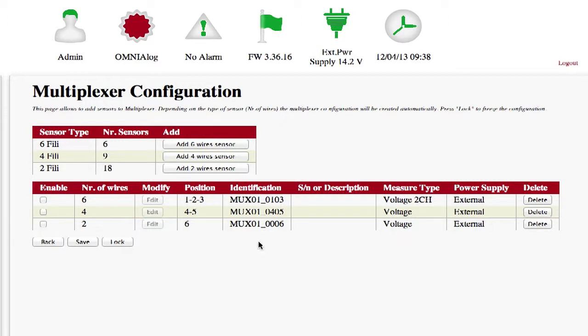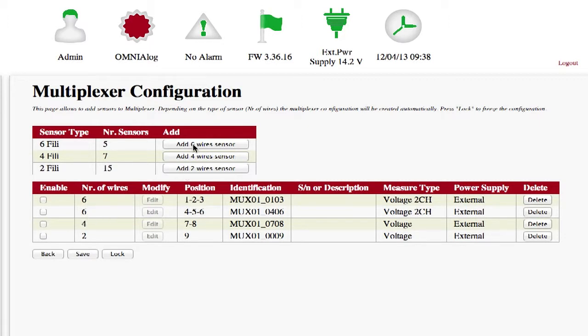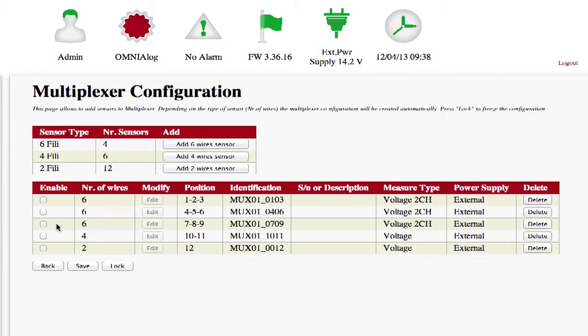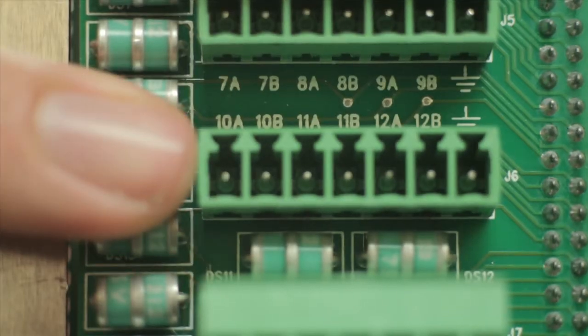The second panel contains a summary of the configuration. The position field is particularly important and shows the cabling position of the instrument connected to the multiplexer board. Omnialog automatically manages the positioning of instruments on the multiplexer, first positioning the group of 6 wire instruments, then the 4 wire instrument group, and lastly the 2 wire instrument group. As a result, after configuring other 2 or 4 wire instruments, a new additional 6 wire instrument will be positioned before those already present, shifting their position on the multiplexer. For example, the fourth instrument should be connected to screw clamps 10A, 10B, 11A and 11B of the multiplexer.